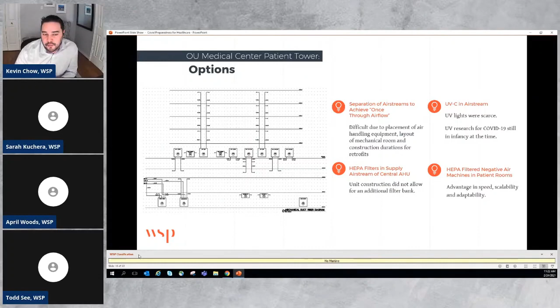We also looked at HEPA filters in the supply airstream. Knowing that the air handling units were already online and in place, we did not have a means to add an additional final filter section, so we were going to have to retrofit the existing air handling units. It posed problems because a lot of other facilities were looking at the same thing, and finding HEPA filter racks and HEPA filters was starting to become a challenge.